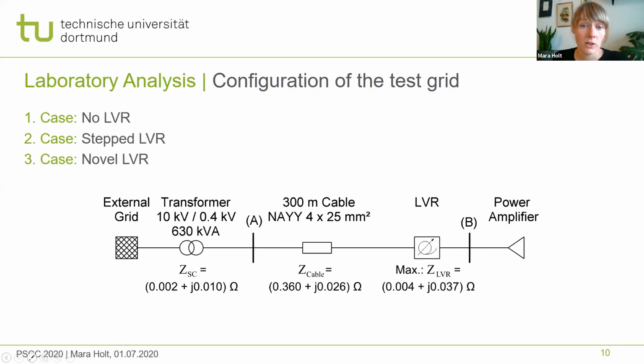In the last part of this presentation, the novel line voltage regulator with a developed control system is evaluated regarding its influence on power quality. For this purpose, the usage of the novel line voltage regulator is compared to the usage of a stepped line voltage regulator. For reference, a setup without any line voltage regulator is also measured. Here you can see the configuration of the test grid in a laboratory. A power amplifier is connected via a 300-meter cable and a transformer to the external grid. Depending on the setup, a voltage regulator technique can be linked in series between the line and the power amplifier. The power amplifier models the feed-in of distributed energy resources.